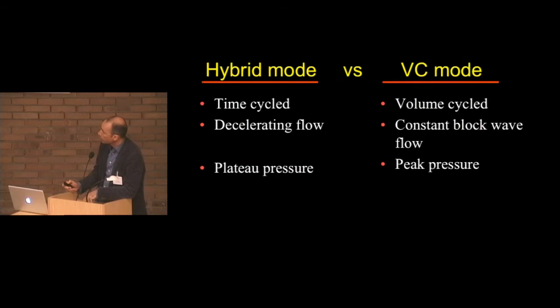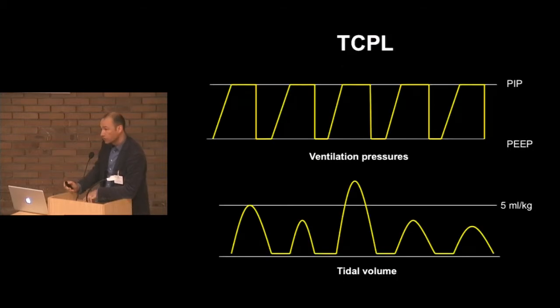So there are basic differences between the hybrid modes and the volume control modes. The hybrid modes are time cycled, so the time set by the clinician will end the inspiration. True volume control is volume cycled. This has a decelerating flow, this has a constant square wave flow. This has a plateau pressure, and this has a peak pressure. So there are differences, although they both try to target a certain tidal volume that is set by the clinician. So how does it work?